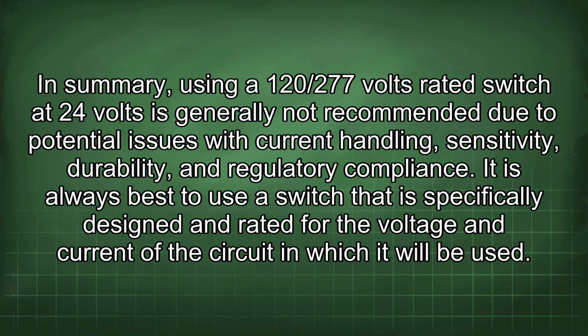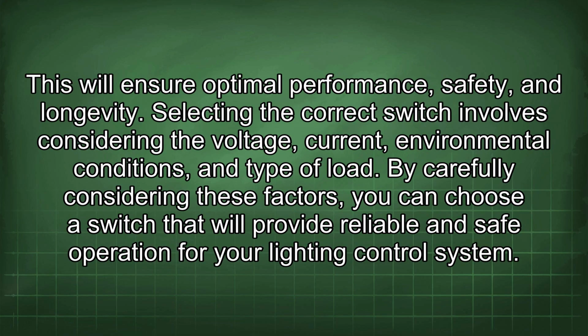120/277 volts rated switch at 24 volts is generally not recommended due to potential issues with current handling, sensitivity, durability, and regulatory compliance. It is always best to use a switch that is specifically designed and rated for the voltage and current of the circuit in which it will be used. This will ensure optimal performance, safety, and longevity.